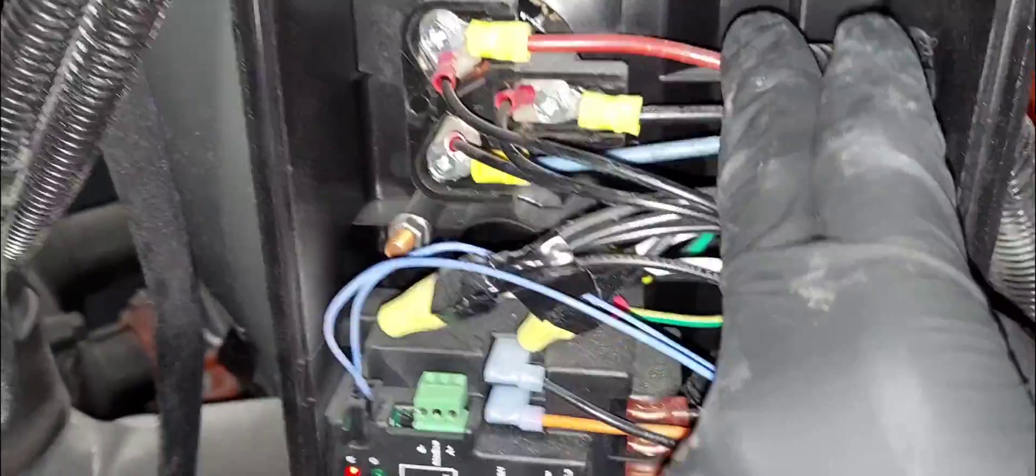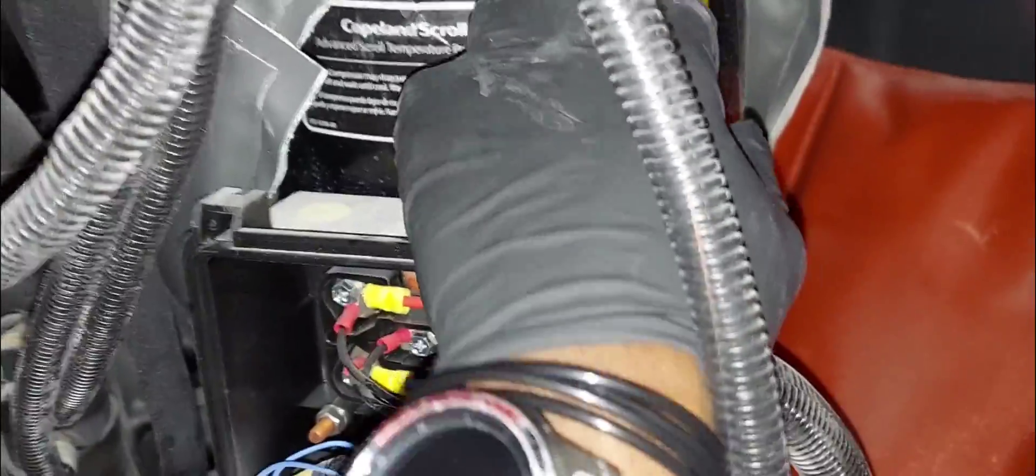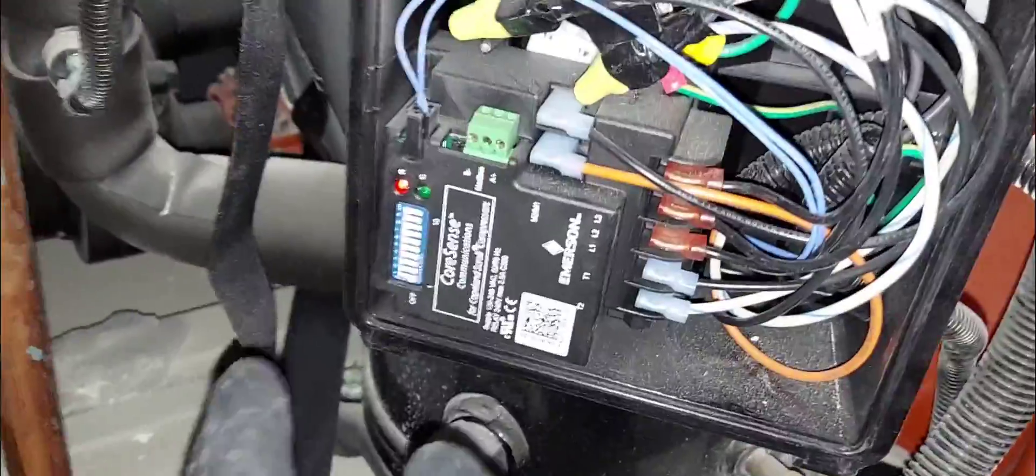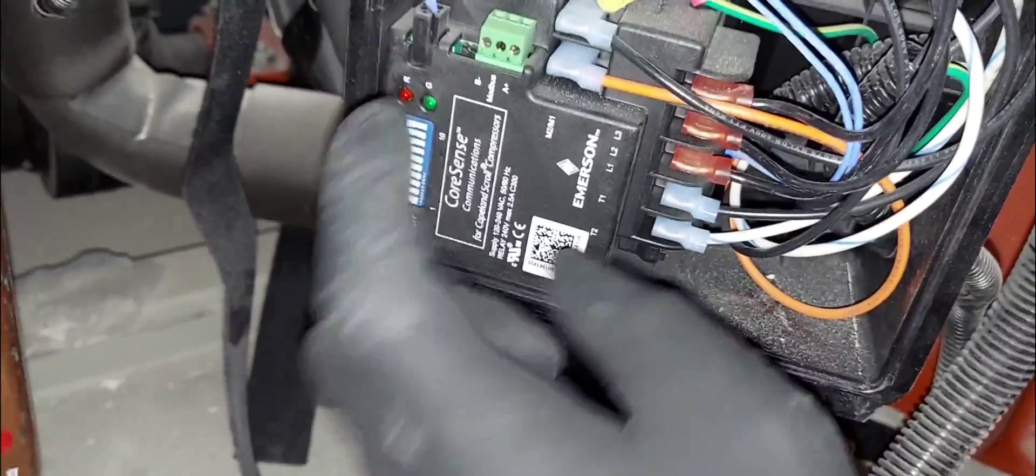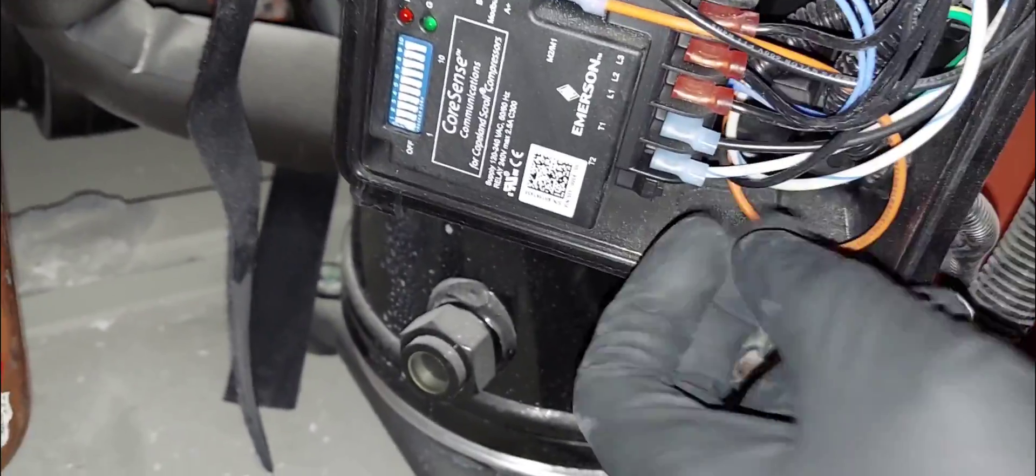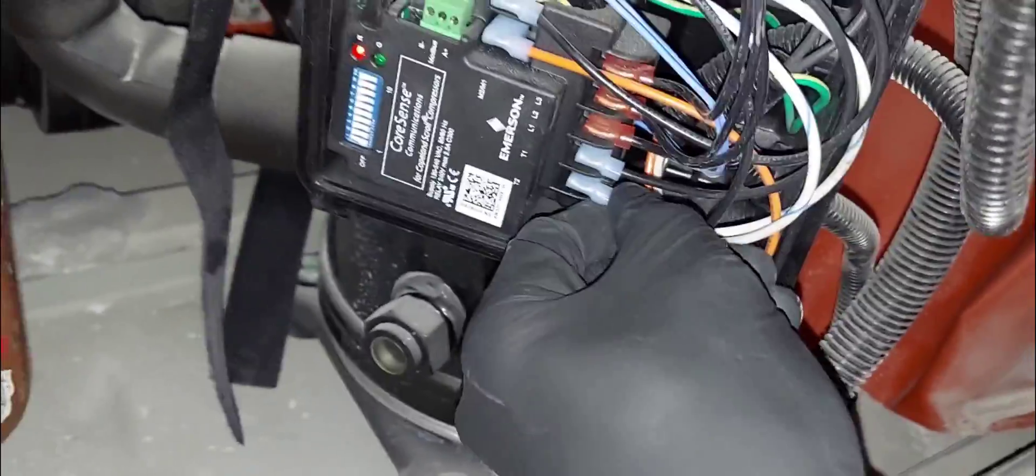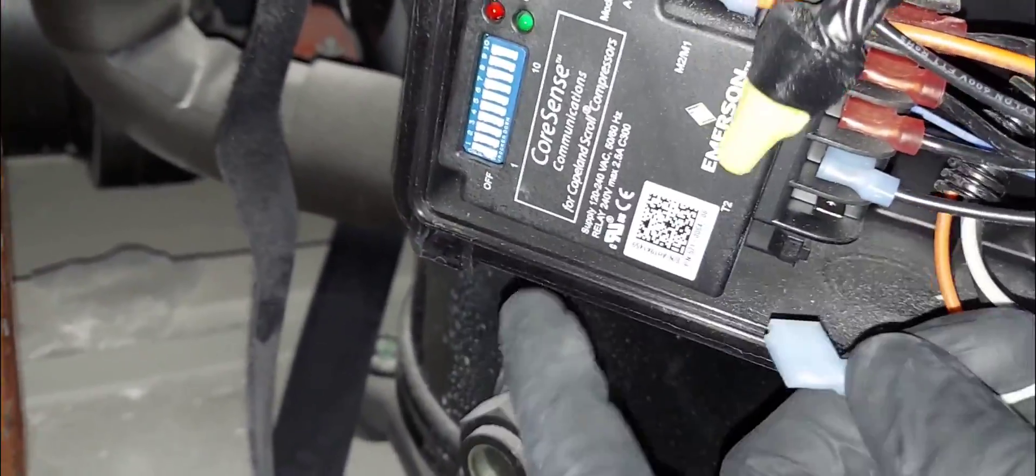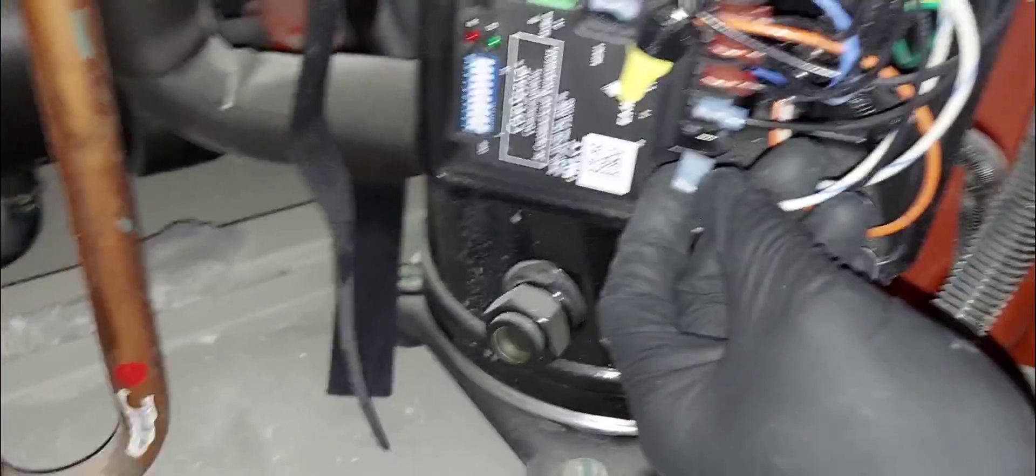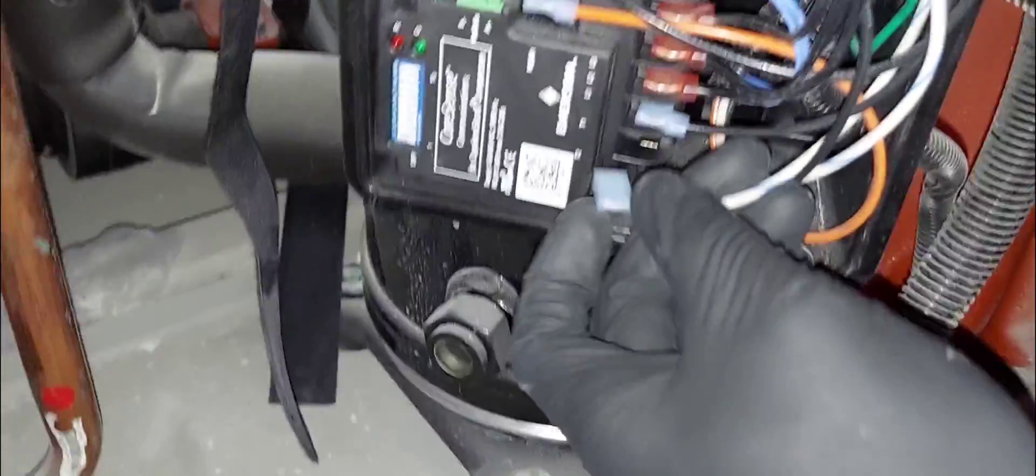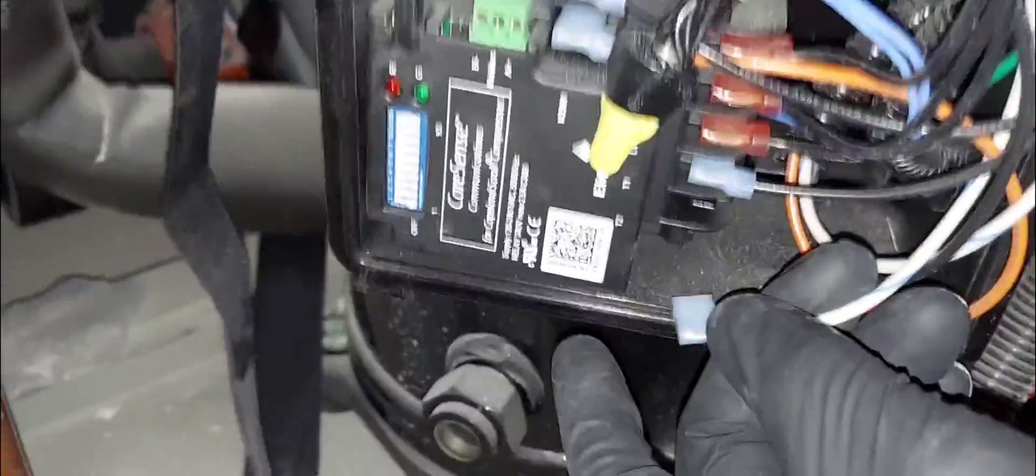The compressor, when it came on momentarily, it sounded from experience like we are in the right or correct rotation. Let's see. To reset this bad boy right here you just got to pull the main power which is this one. So once you disconnect the main power which is T1 and T2 - now if you want to know about this motor protector CoreSense, I have a video on that. I'm going to leave the link in the description so you guys could watch it where I explain in depth how this thing works. I'm going to pull the power - you can see there's no light - and I'm going to put it back.